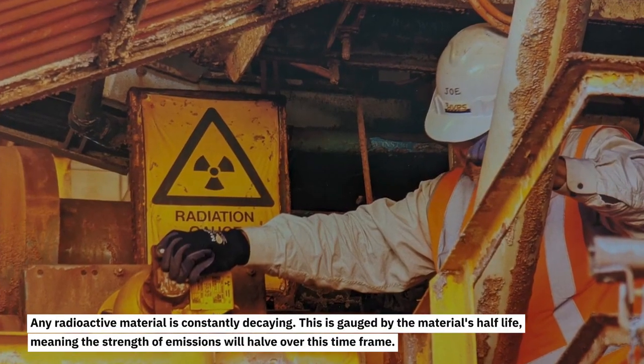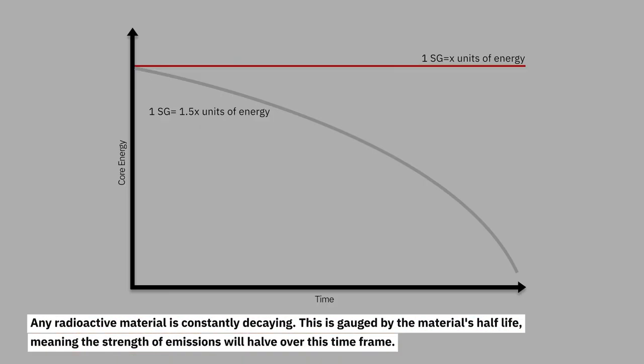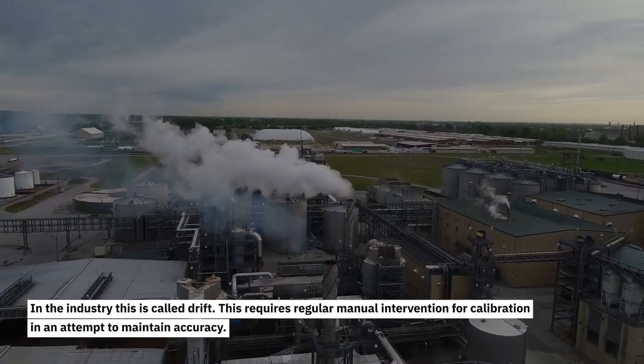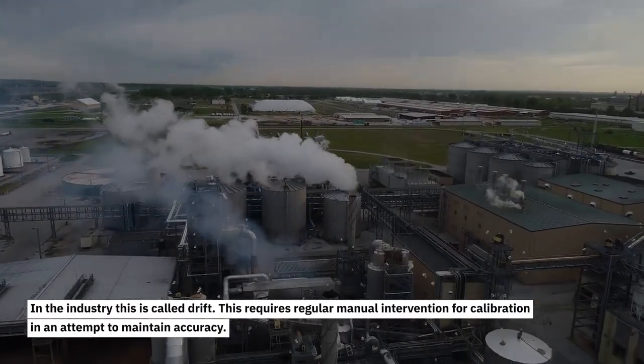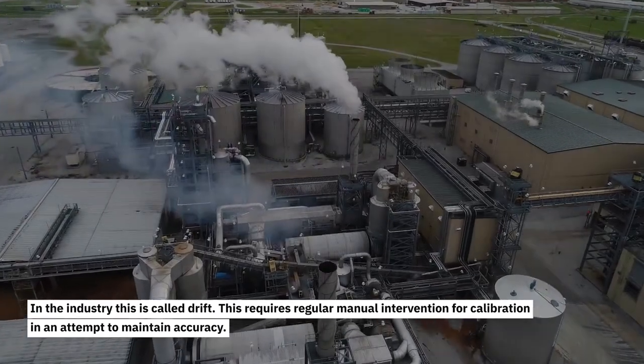Any radioactive material is constantly decaying. This is gauged by the material's half-life, meaning the strength of the emissions will halve over this time frame. In the industry, this is called drift. This requires regular, manual intervention for calibration in an attempt to maintain accuracy.